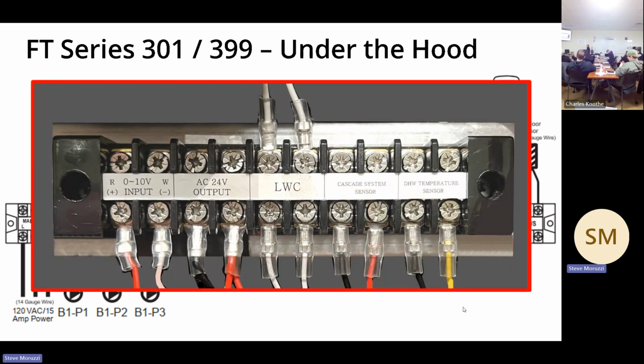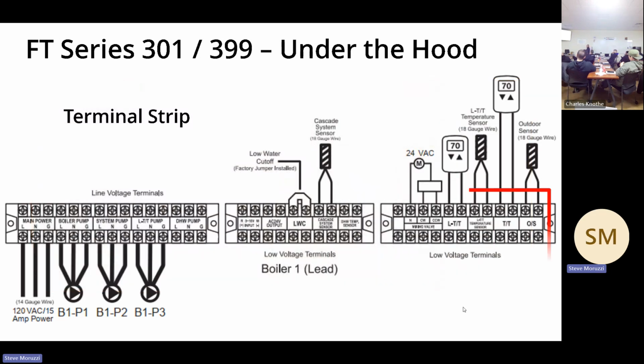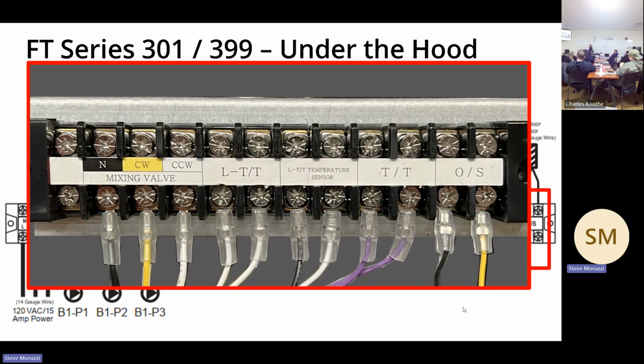Next here on the low voltage, there's your 0 to 10, so Tekmar controls or whomever want to control the modulation. 24-volt output is strictly for that low water, additional low water cutoff that you guys are required to have on the system. And it is a heating boiler, so we can do cascading up to 4. So we're gonna have the cascade sensor and DHW temperature sensor or aquastat for your indirect tank. And lastly, if we're gonna control a 3 or 4-way mixing valve, we can do that with the 24 volts.